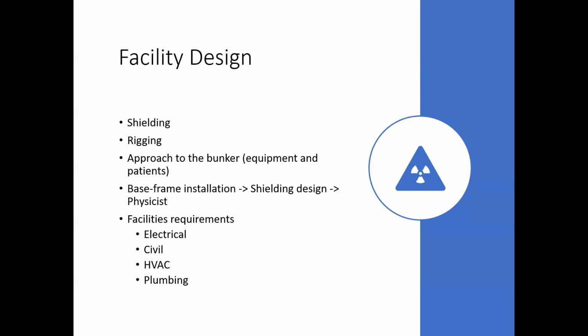Rigging is an important part, as I already told you. We should consider the approach to the bunker for the equipment and the patient. Base frame installation may affect the shielding design. For example, we have designed a facility and made decisions on the shielding design on the basis of putting an ISO center at a position, but if we end up with wrong base frame installation, this will compromise all our shielding study.